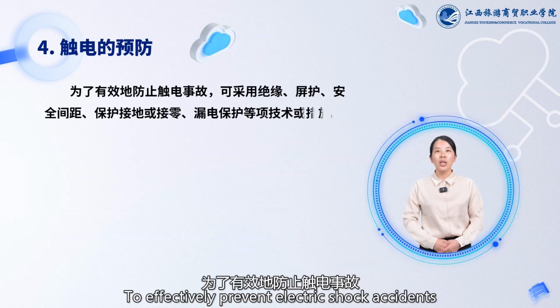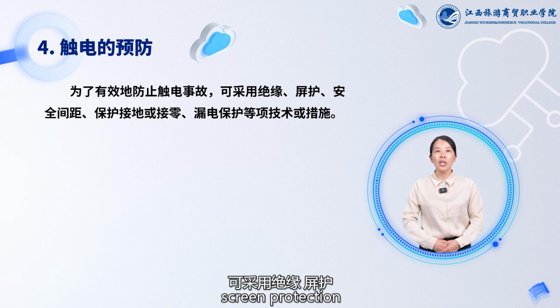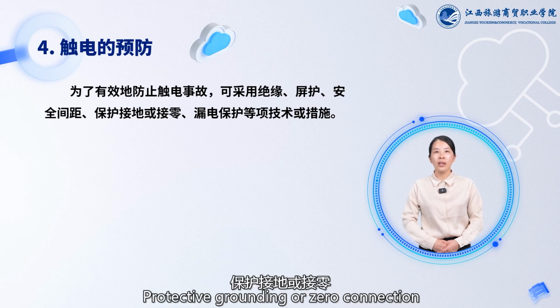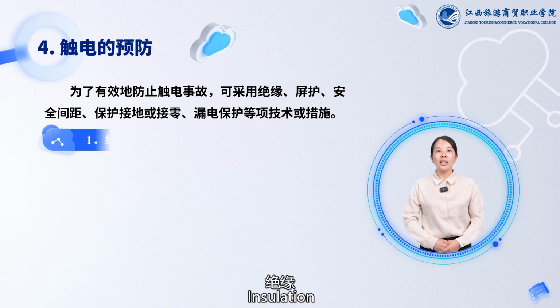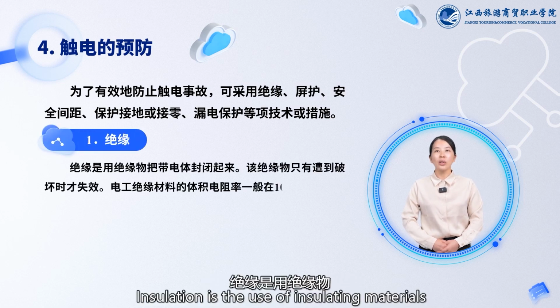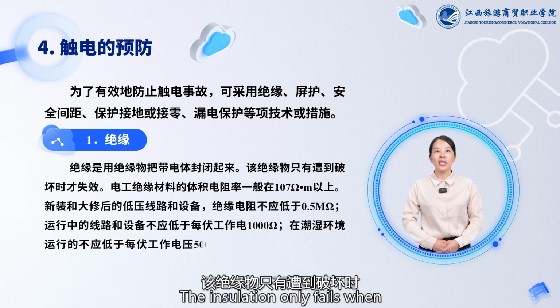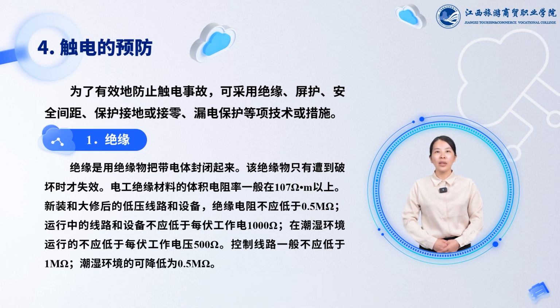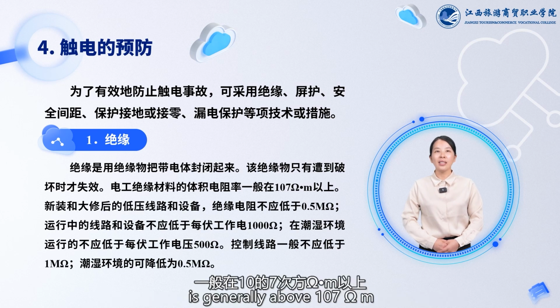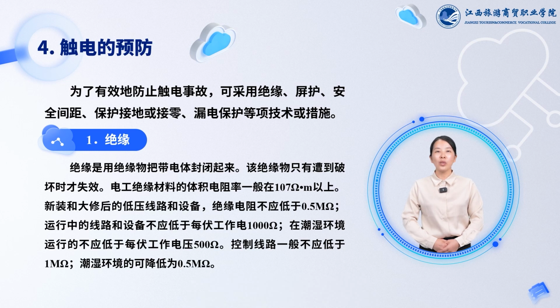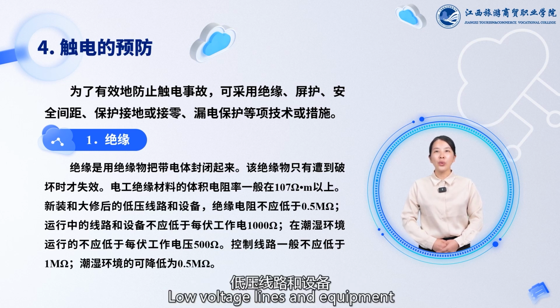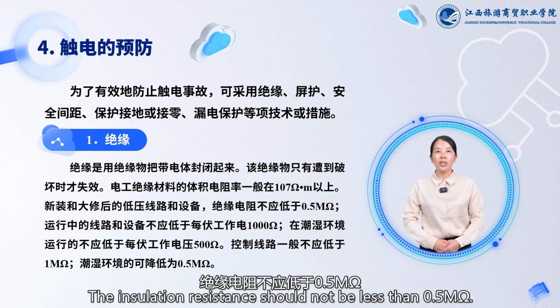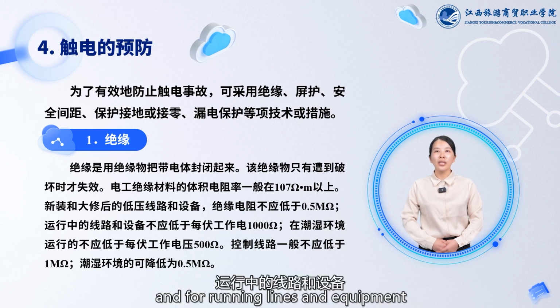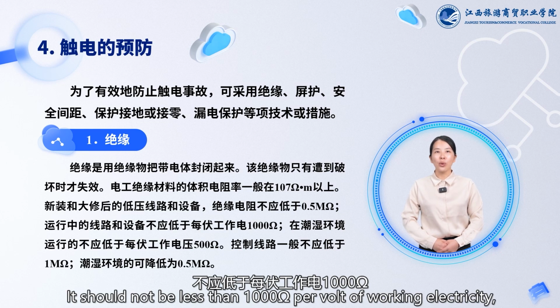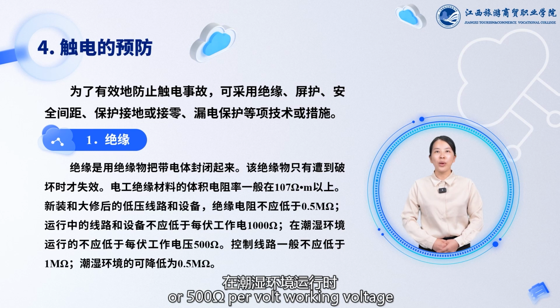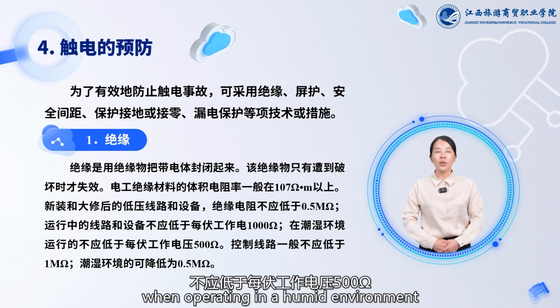To effectively prevent electric shock accidents, measures such as insulation, screen protection, safe spacing, protective grounding or zero connection, and leakage protection should be employed. Insulation. Insulation is the use of insulating materials to enclose the charged body. The insulation only fails when it is damaged. The volume resistivity of electrical insulating materials is generally above 10 to the power of 7 ohm meter. For newly installed and overhauled low voltage lines and equipment, the insulation resistance should not be less than 0.5 megaohm. And for running lines and equipment, it should not be less than 1000 ohm per volt of working electricity, or 500 ohm per volt working voltage, when operating in a humid environment.